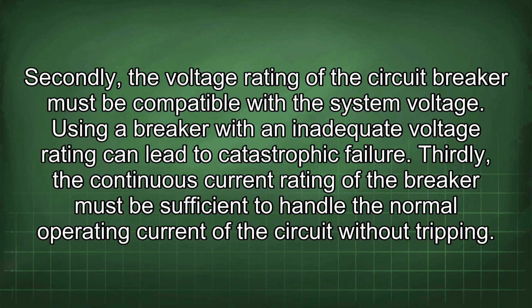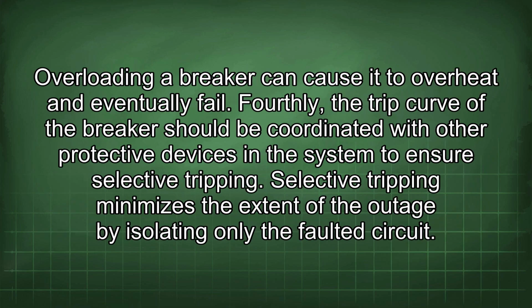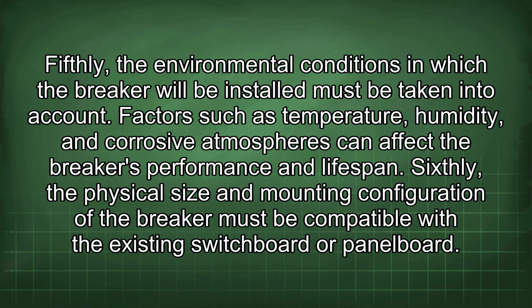Using a breaker with an inadequate voltage rating can lead to catastrophic failure. Thirdly, the continuous current rating of the breaker must be sufficient to handle the normal operating current of the circuit without tripping. Overloading a breaker can cause it to overheat and eventually fail. Fourthly, the trip curve of the breaker should be coordinated with other protective devices in the system to ensure selective tripping. Selective tripping minimizes the extent of the outage by isolating only the faulted circuit. Fifthly, the environmental conditions in which the breaker will be installed must be taken into account. Factors such as temperature, humidity, and corrosive atmospheres can affect the breaker's performance and lifespan.